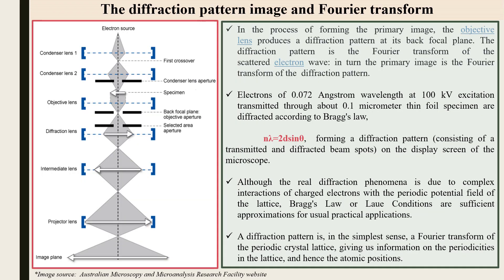Moving on to the diffraction pattern and Fourier transform: in the process of forming a primary image, the objective lens produces a diffraction pattern at its back focal plane, where the objective aperture is located. The diffraction pattern is a Fourier transform of the scattered electron wave, and in turn the primary image is a Fourier transform of the diffraction pattern.